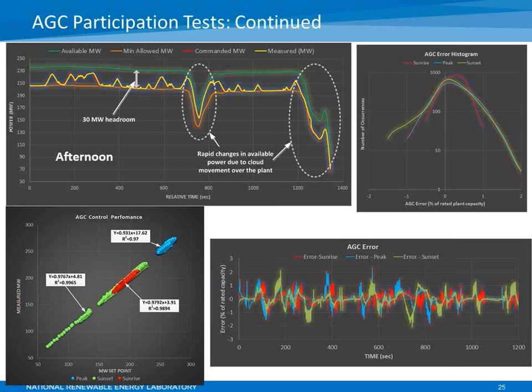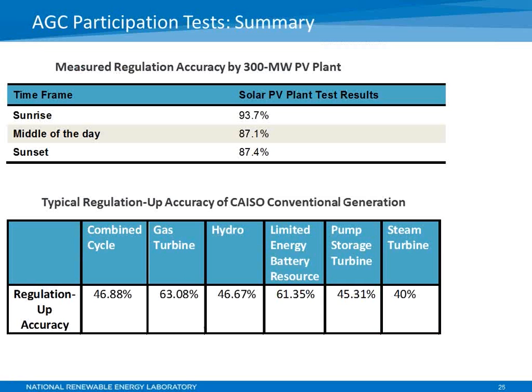Another time series on the bottom right is the AGC control error expressed as a percentage of plant rated capacity. You see that the maximum error there is within plus or minus 2%, which roughly translates into plus or minus 5 megawatts or so of power. This can be corrected with a very small amount of energy storage, but what is most important, this can be corrected by geographical diversity. As more and more PV plants participate in this type of service, the aggregate accuracy of a whole PV fleet will be much better in per unit, because the main component in this AGC error is a small amount of resource variability, which is random in nature, and it's anticipated to be smoothed out as larger plants participate in this.